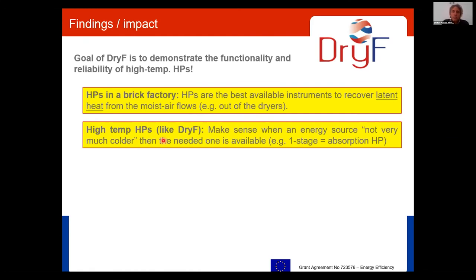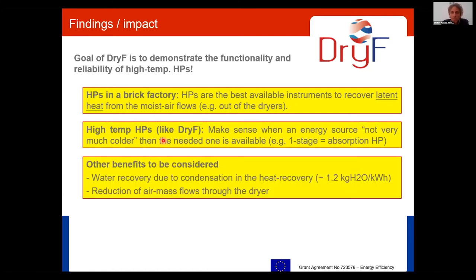The high temperature heat pump, like DryF, makes sense when there's an energy source available that is not too far away and not much colder than the temperature we need in the dryer. And this depends on the size of the building. Like in Uttendorf, we need temperatures above 90 degrees. Then DryF can be connected to an absorption heat pump system and makes a really interesting solution.